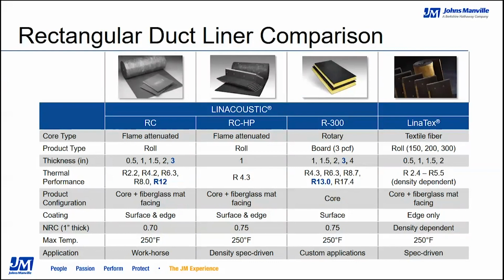The one thing I want to point out here is the NRC rating, or noise reduction coefficient, which is basically the ability of a product to absorb sound as it's traveling down the duct. NRC is rated on a scale of 0 to 1, so at a 0.70 with a 1-inch thick product, that means that duct liner is absorbing 70% of the sound as it's traveling down the duct, doing a nice job of mitigating and eliminating that noise.